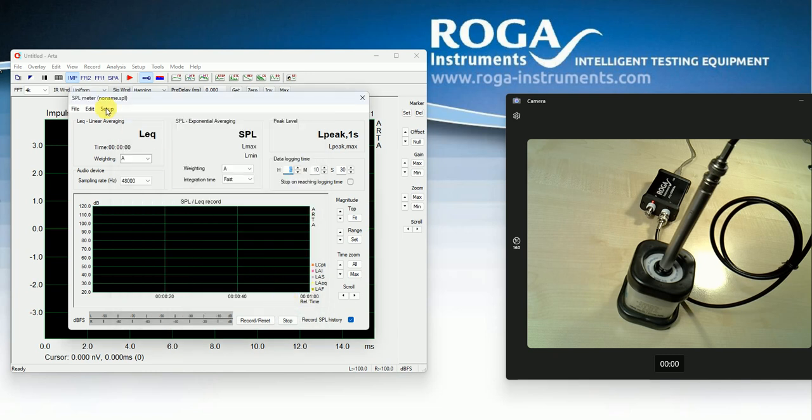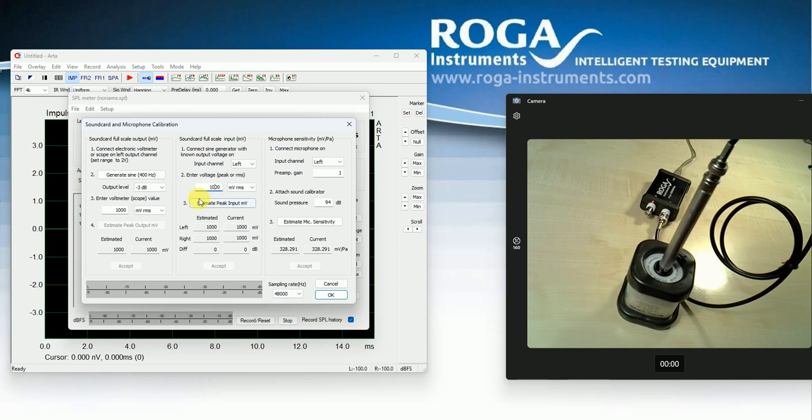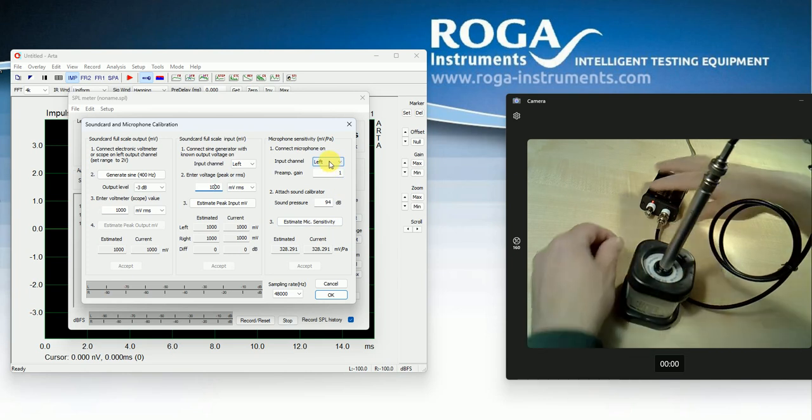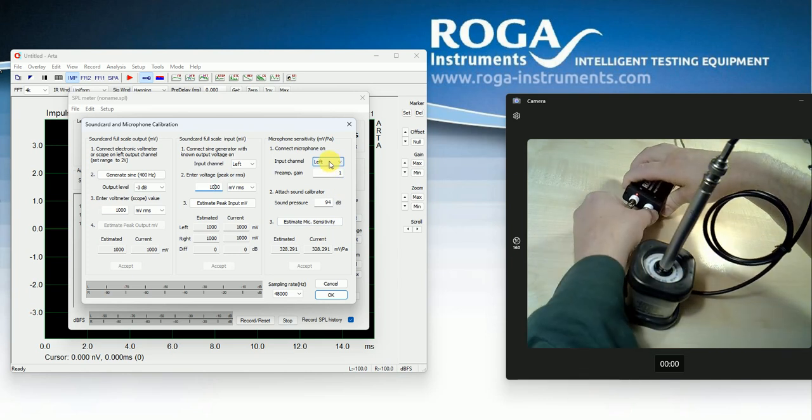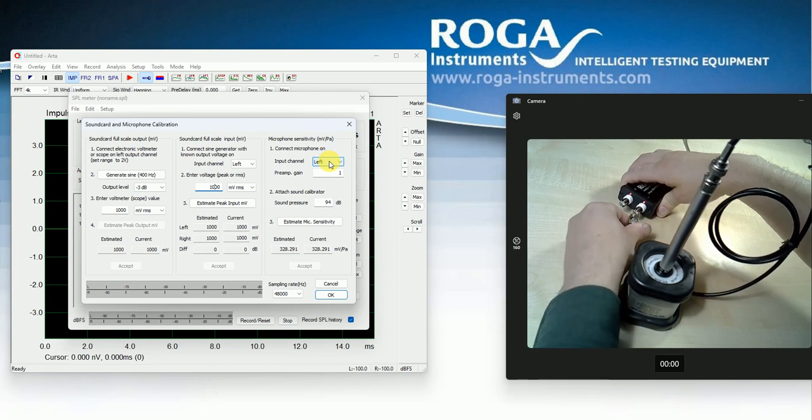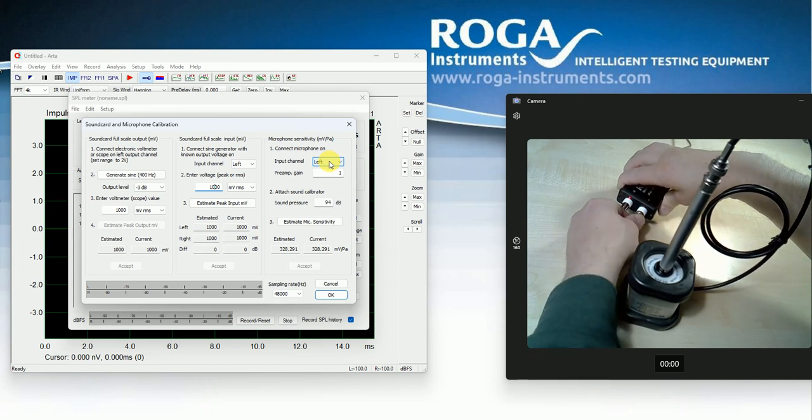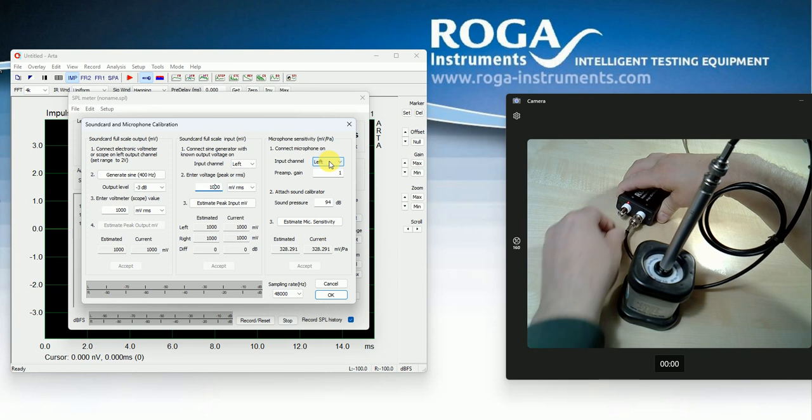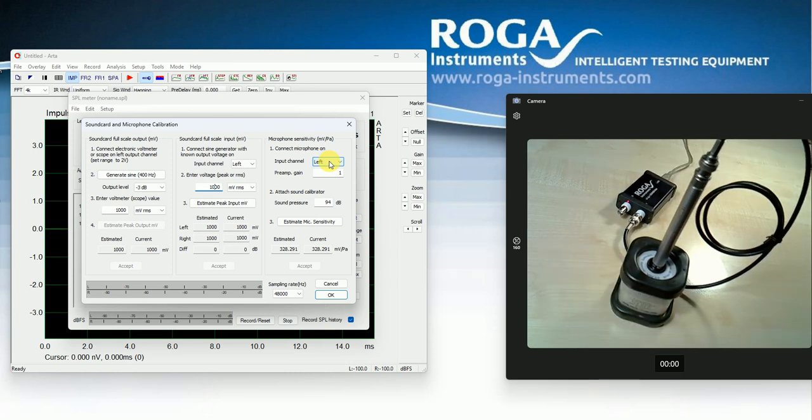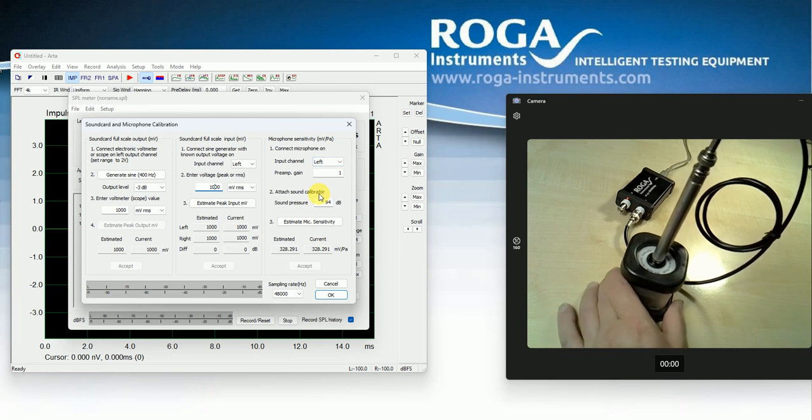So next I calibrate. So I enter here again 1000 millivolt. So the microphone is connected at the channel number 1, means left channel. So the microphone calibrator delivers 94 dB.